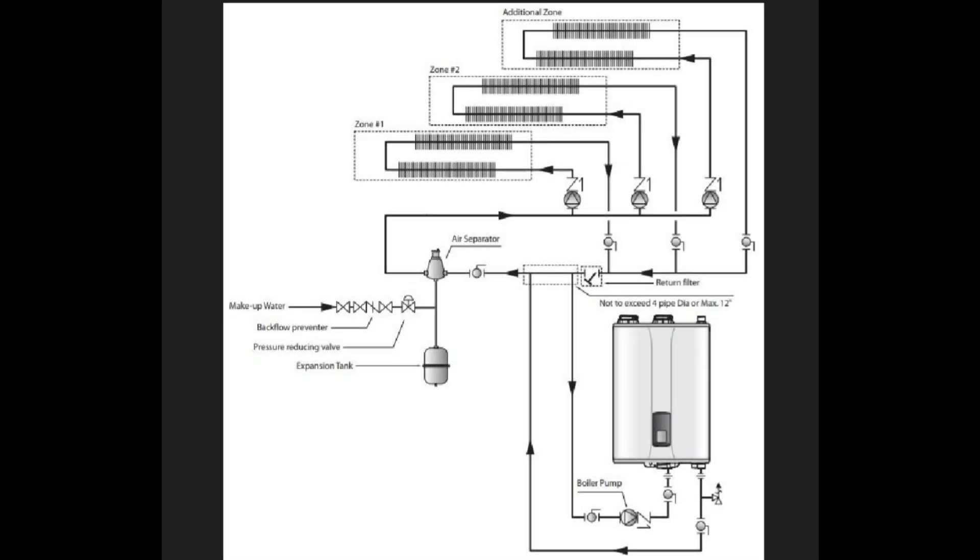Now, as for the rest of the piping on a combi boiler, it's very similar to your standard hydronic boiler. This is our closely spaced T's here, right? So we got our T here and our T here spaced closely together. Here we have our makeup water coming in. And it's going to go up into an air separator. So we're going to have an air scoop or a spiral vent or something.